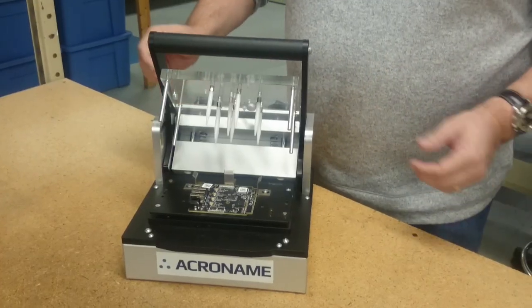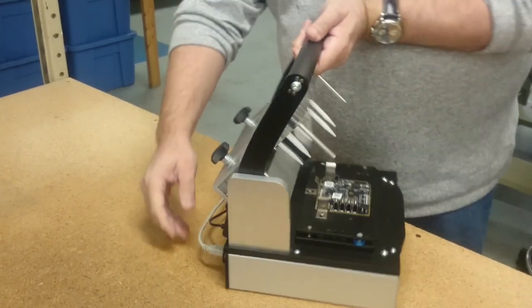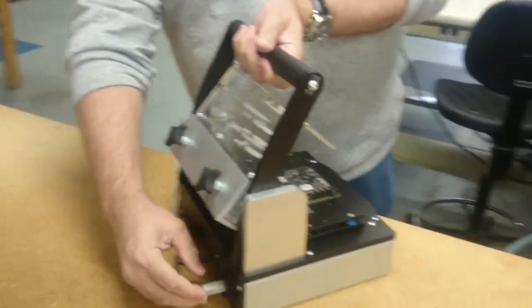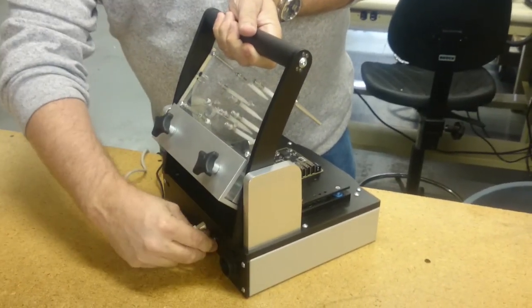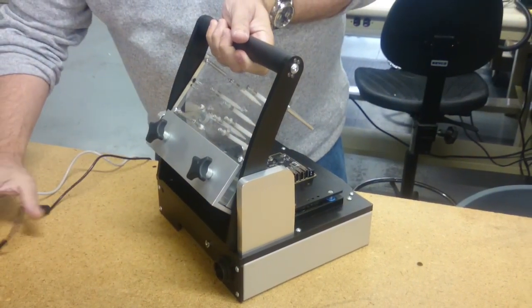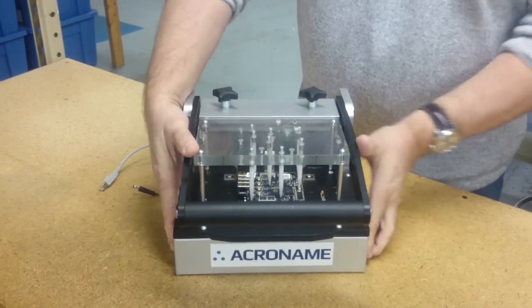Now that we're done testing, we can swap out the Acroname ATS module and the fixture top plate for another DUT. This implementation here really exploits the modularity of the Acroname fixture and of the MTM modules.